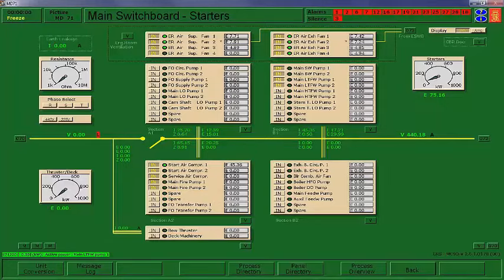All right, so I'll go ahead and start it. The first thing we're going to do is put on the, what are we going to need? Well, we're going to be getting the high temperature fresh water system ready, and we're not going to use these pumps per se, but I want that system operational and ready to go when we're finished. So we'll put power to the main high temperature fresh water pumps, the exhaust boiler circ pumps, exhaust boiler compression air combustion air fan, heavy fuel oil, diesel oil pump, all of those. Main feed water, auxiliary feed water. These are all off the starters.